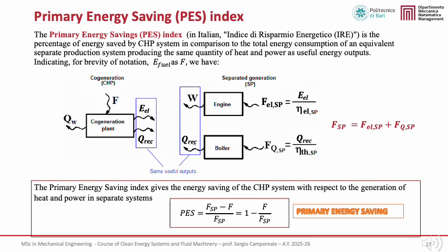In this slide, we introduce the Primary Energy Saving, or PES index. The PES index is the indicator adopted by the European Union to quantify the energy benefit of cogeneration. The PES index measures the relative primary energy saving achieved by a cogeneration system compared to an equivalent reference system that produces the same useful outputs, namely electricity and useful heat, using separate conventional technologies.